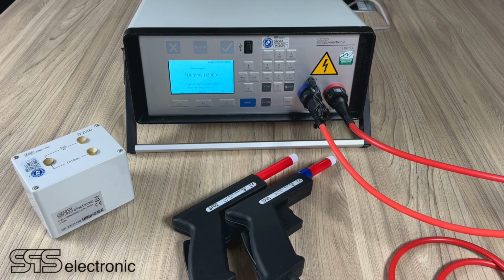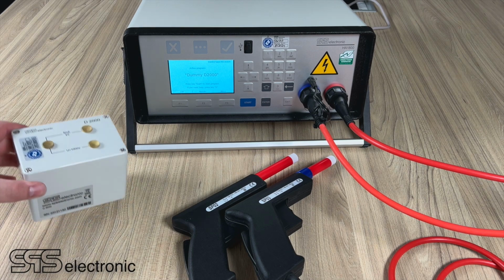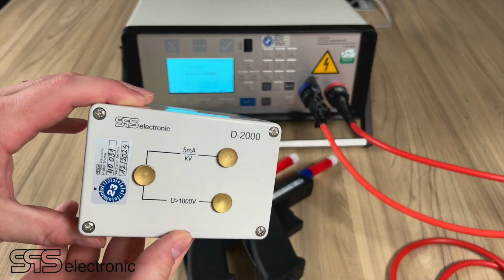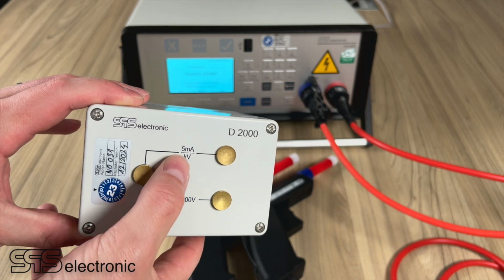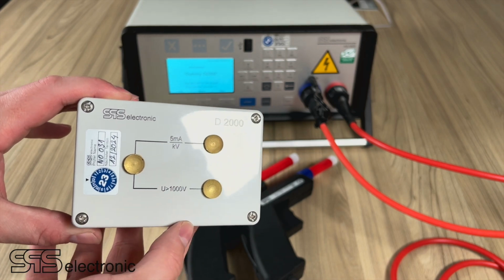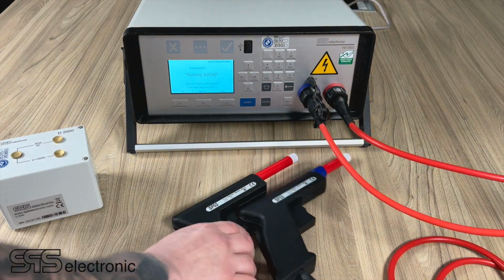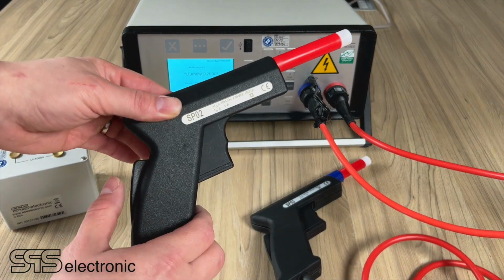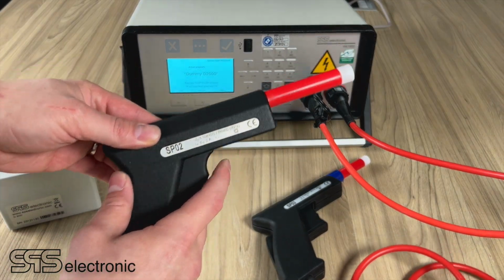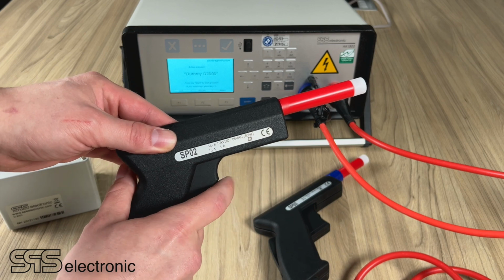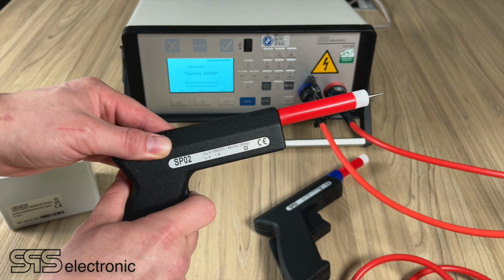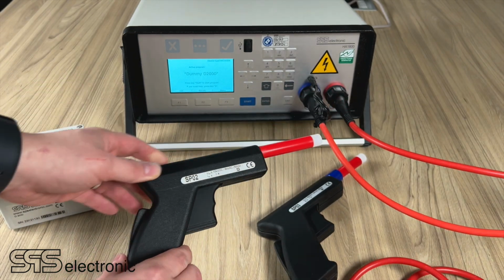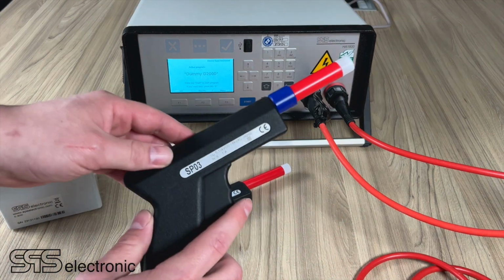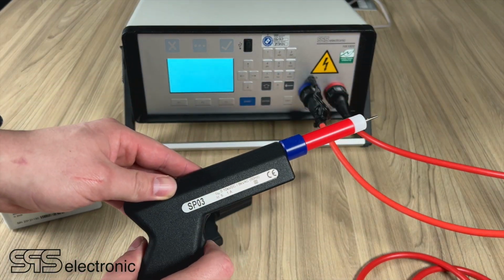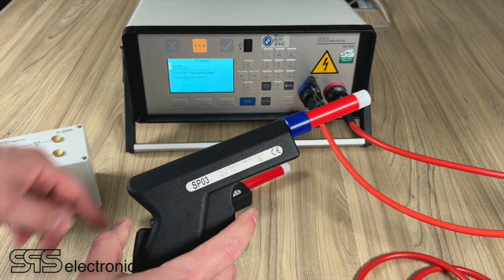And this is the setup for today. I will use our test dummy for high voltage testing. First measuring will be standard measuring of the current, and the second one is for short circuit at 1 kV. I will use our high voltage pistols, which have a safety contact from behind. That means you have to press it with the whole hand when the pins come out. The first, SP02, is without the start button, but the second one, SP03, will start the test for us, as you can see on the display.